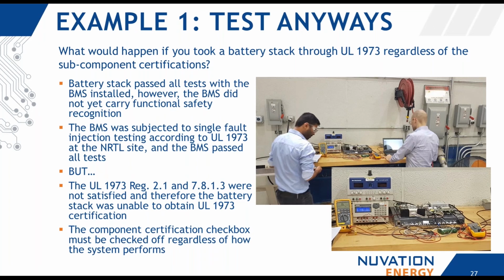So when they got to that point, the BMS was then subjected to single fault testing. And so these photos are actually of a site in the US where you had to go and bring the ability to inject open circuit and short circuit faults within the BMS product and demonstrate that in all conceivable instances, the BMS will fail safely. And so we did this, and it passed all the tests. But what it came down to at the end of the day was a checkbox. The requirements 2.1 and 7.8.1.3, which relate to the components used having to meet their required certification, were still outstanding. And so as a result, the 1973 stack certification was incomplete.